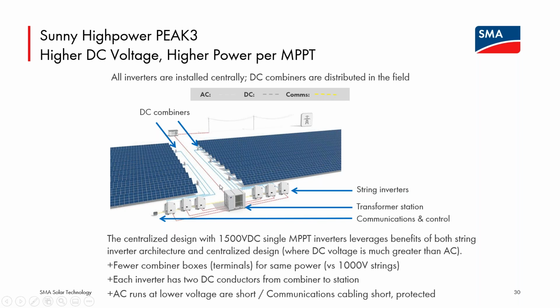So have the combiner boxes out at the array, but not the inverters. Have them in a centralized location where the AC runs to a step-up transformer or the point of interconnection are as short as possible to minimize those losses. If the inverter is outputting full power on the AC side, any line losses past the inverter cannot be overcome by the inverter. They are simply losses. But if you have line losses on the DC side, you can potentially size up the DC to AC ratio and compensate for those losses while still having the inverters outputting maximum power, maximum potential revenue. So again, another reason having the AC runs as short as possible is generally recommended.